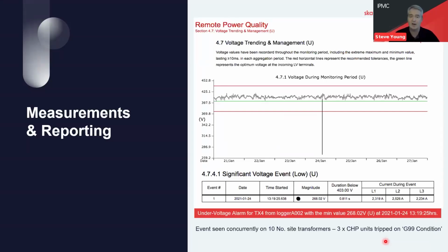Particularly if we have permanent monitoring, this is particularly useful. And this is something that is available now with the likes of the remote power quality system, which is very clever in the way that it picks up 10 millisecond events constantly, raising alarms. And this gives us the ability to capture events and associated inrush currents at very, very fast occurrence rates, and we're able then to provide useful information back to facility operators.